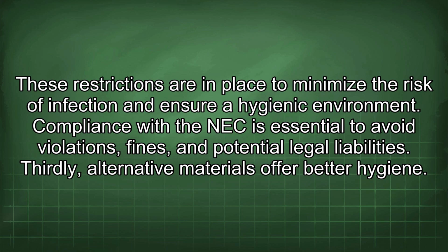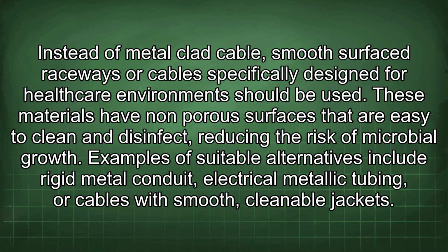Thirdly, alternative materials offer better hygiene. Instead of metal-clad cable, smooth surface raceways or cables specifically designed for healthcare environments should be used. These materials have non-porous surfaces that are easy to clean and disinfect, reducing the risk of microbial growth. Examples of suitable alternatives include rigid metal conduit, electrical metallic tubing, or cables with smooth, cleanable jackets.